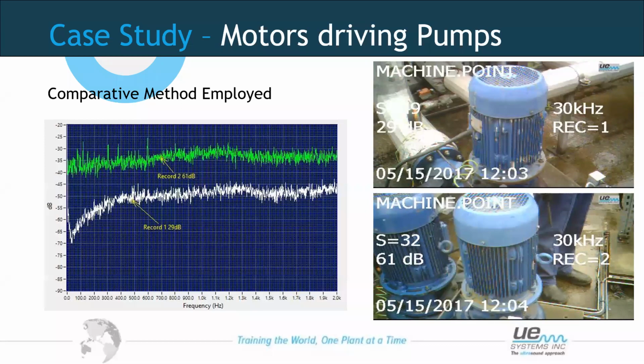Okay, so this motor, after this demonstration, was taken out of service, and they reported back to me that when they took it out of service, the drive end bearing fell apart in their hands. It was on the verge of failure. So again, another good find on a fortunate demonstration at the time.